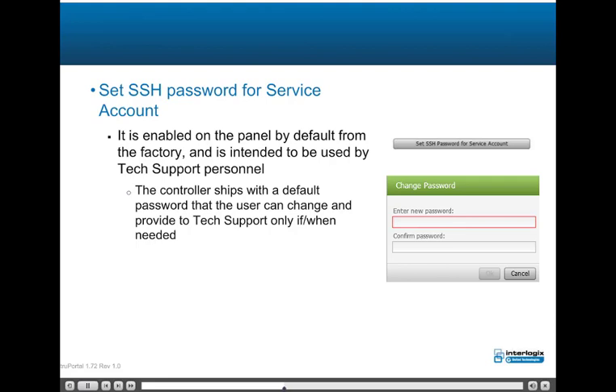Set SSH password for service account is enabled on the panel by default from the factory and is intended to be used by tech support personnel, not by the TruPortal system user. The controller ships with a default password that the user can change and provide to tech support only when needed. An option is provided to disable SSH completely, but it is not recommended because if the web app cannot be brought up to re-enable it, there is no way for tech support to service the panel, and it would need to be replaced or require on-site service.